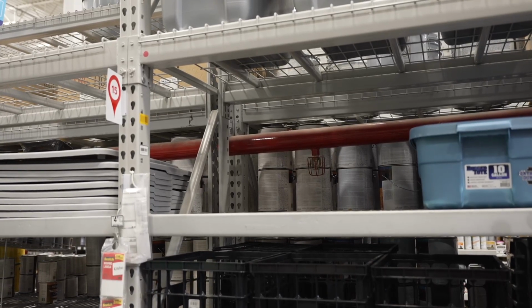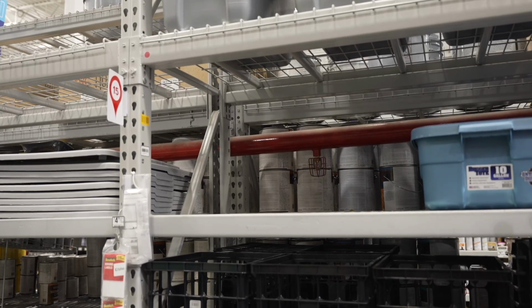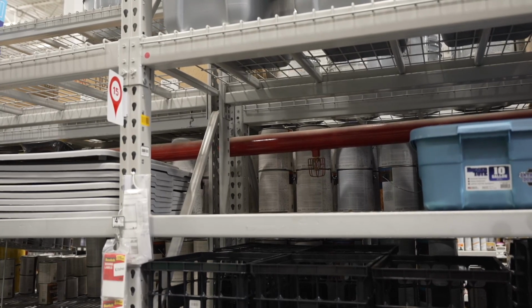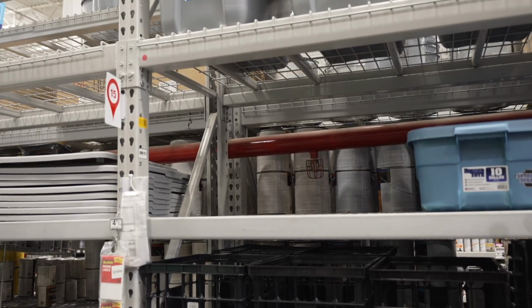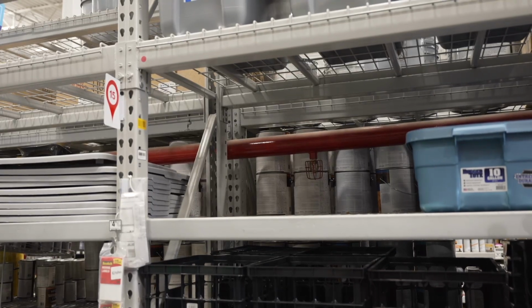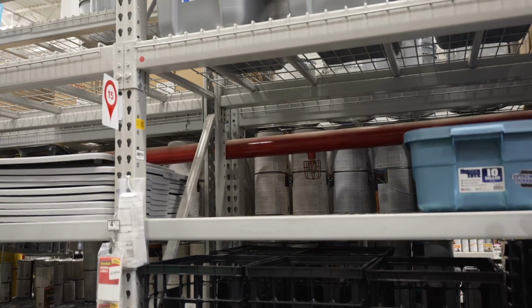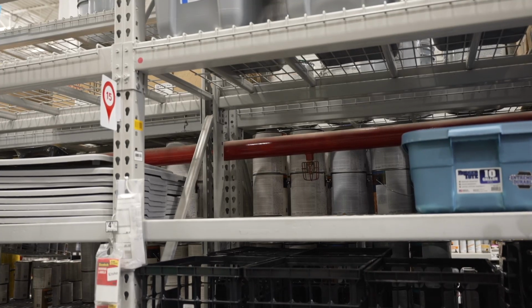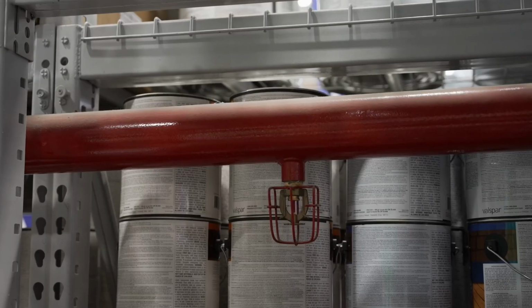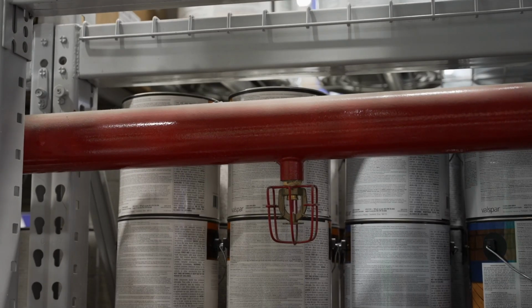All right, in most mercantile, you're going to have storage above 12 feet, which is considered high-piled combustible storage. Because of that, they'll have what you call in-rack sprinkler protection. You need to look and make sure the little cages are on the sprinklers in every instance where they're in the racks.